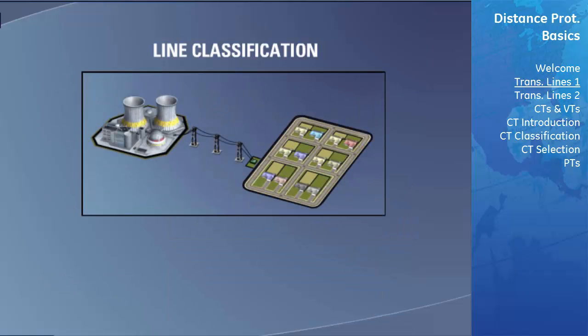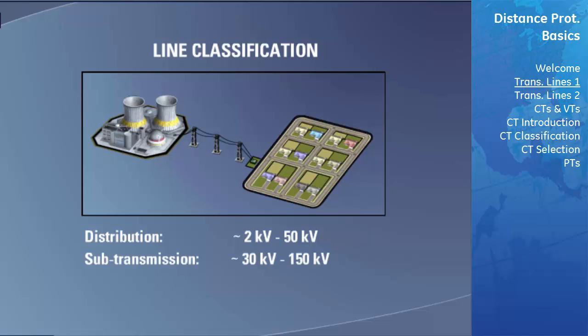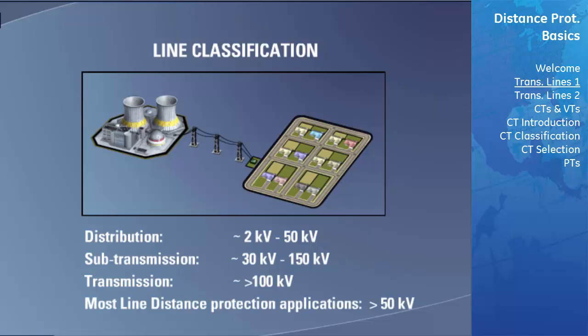The voltages used for transmission of power over transmission lines are split into three categories. Distribution levels are in the range of 2 kilovolts to 50 kilovolts. Sub-transmission levels are in the range of 30 kilovolts to 150 kilovolts. Transmission levels are greater than 100 kilovolts. Most applications that use distance protection are 50 kilovolts or greater.